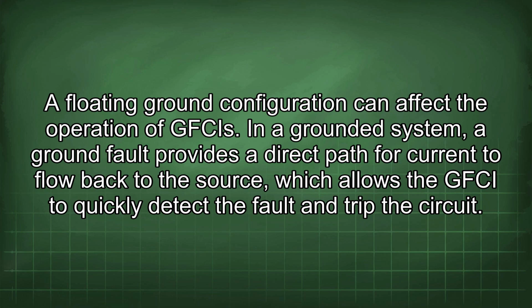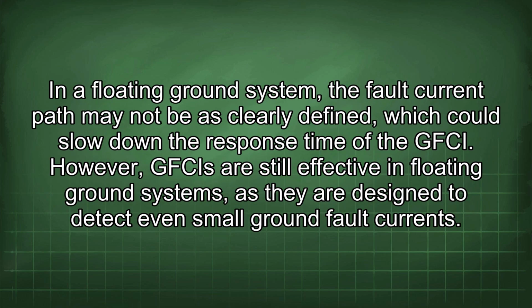In a grounded system, a ground fault provides a direct path for current to flow back to the source, which allows the GFCI to quickly detect the fault and trip the circuit. In a floating ground system, the fault current path may not be as clearly defined, which could slow down the response time of the GFCI. However, GFCIs are still effective in floating ground systems, as they are designed to detect even small ground fault currents.